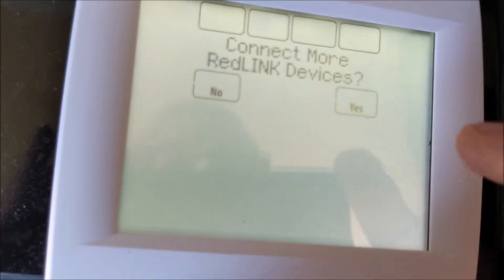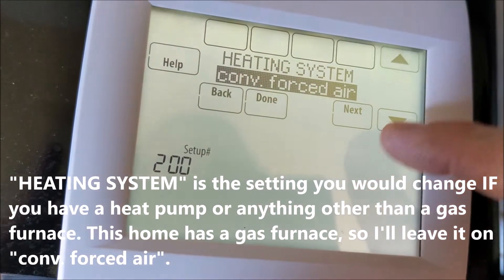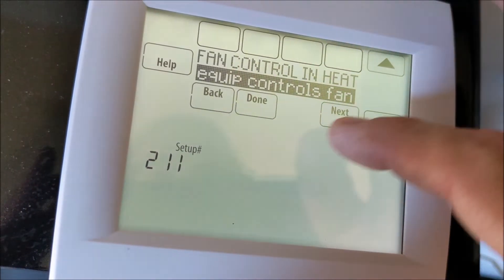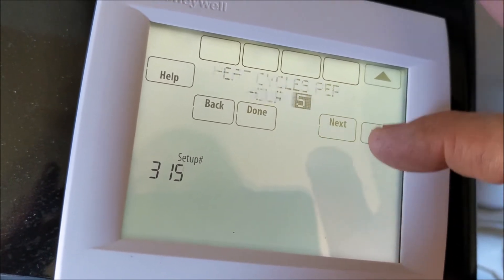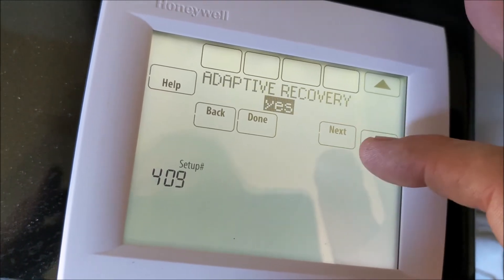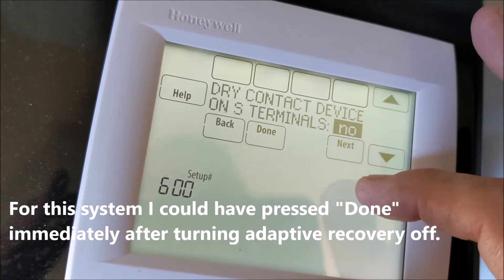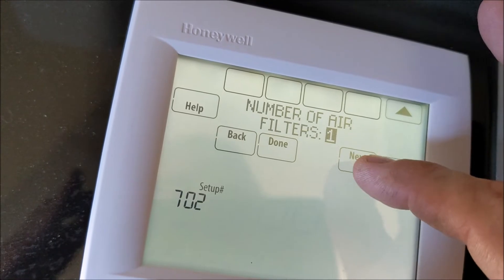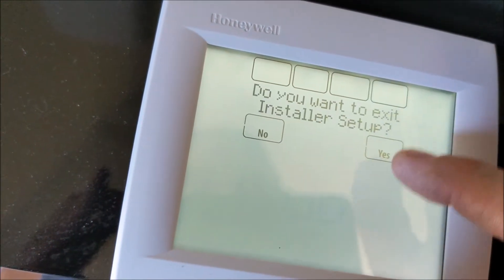Then you hit done, and then no more Red Link devices. Press next. It's programmable. Fahrenheit. No outdoor air sensor. Conventional forced air. Cool stages. Heat stages. Equipment controls. I'm going to turn adaptive recovery off. Basically, that's it. Hit done, yes. It made us wait five minutes, but then it turned on. The heat-cool fan lights are on, so it appears to be working.